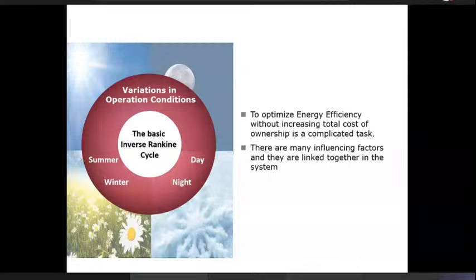So here is the case, the temperature will go up because of the ambient temperature going up, and it will come down when the ambient temperature comes down. They are able to adapt to load and then allow the heat exchangers to have lower temperature difference. If we had, let's say, 50% of the capacity required at night for a residential air conditioner, it would be possible to make use of a lower temperature difference and get a higher efficiency because of a lower refrigerant flow rate. So the heat exchanger surface area continues to be available to us, but the cooling load has reduced, so we can reduce the refrigerant flow rate and we can benefit from a shift in load and reduce delta T on the evaporator side.